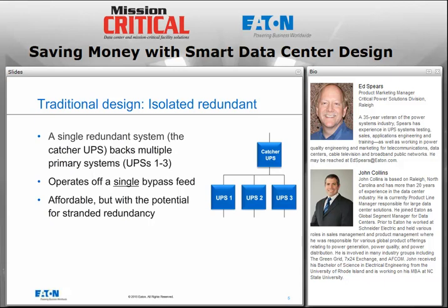However, it did have some disadvantages. For example, it operated off of a single bypass feed. If that bypass feed disappeared, then that complicated the operation of the system. It was affordable, but it did have the potential for what's called stranded redundancy. In other words, if, let's just say, UPS 1 suffers a failure, then the catcher UPS would then often be dedicated to supporting UPS 1, which means that if UPS 2 or UPS 3 developed a subsequent problem, the catcher UPS says, hey, I'm busy, going to have to do something else.